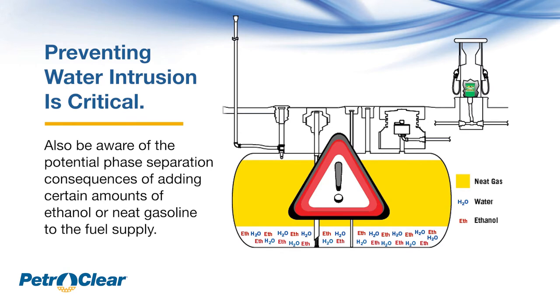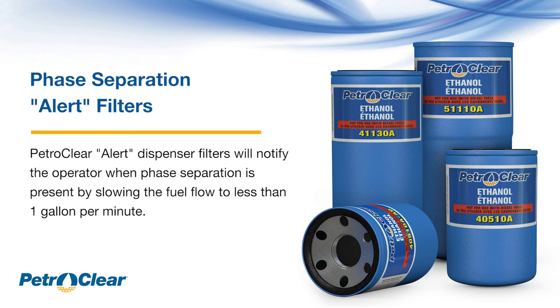The ability of water to enter the fuel stream makes it vital for those handling fuels that contain ethanol at any level to be extremely vigilant in preventing water from getting into their fuel supply. If a marketer is buying fuel, he has to be aware of the potential phase separation properties of adding certain levels of ethanol or neat gasoline fuels to his supply. Switching back and forth to ethanol in a tank lowers the alcohol level and can make the total tank prone to phase separation. When dispensing fuels containing ethanol, a proper filter is the answer for detection of phase separation. Special phase separation alert dispenser filters have been developed by PetroClear that will notify the operator of the condition by slowing fuel flow to less than one gallon per minute. This slow flow condition is a signal that phase separation is present and that the tank contents should be tested.